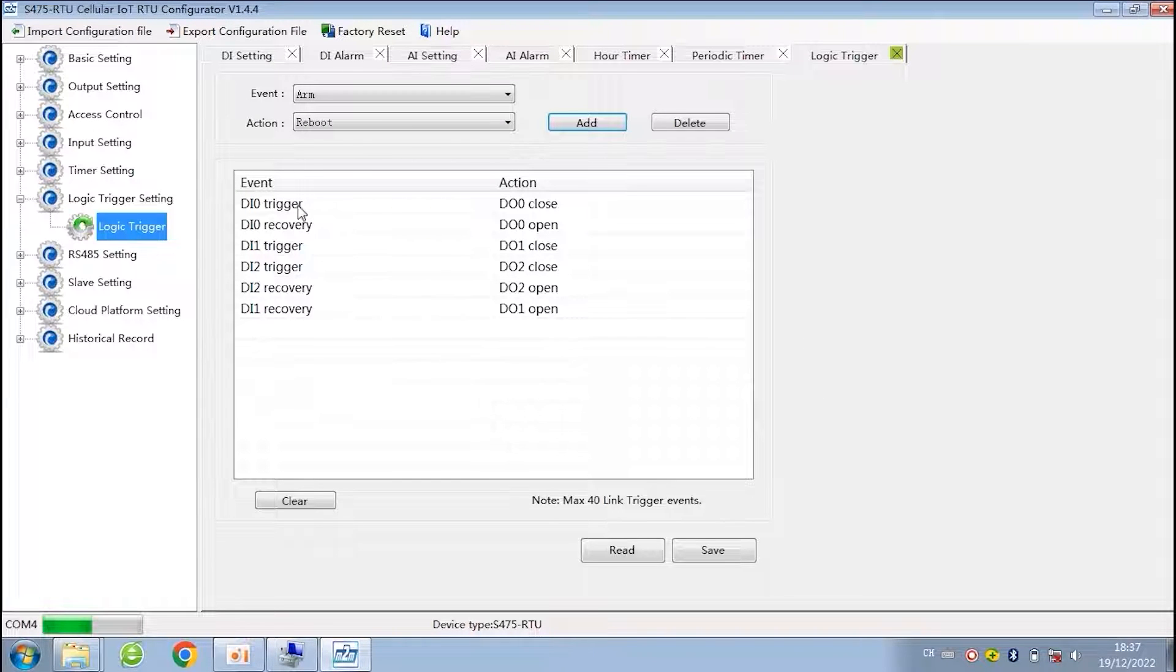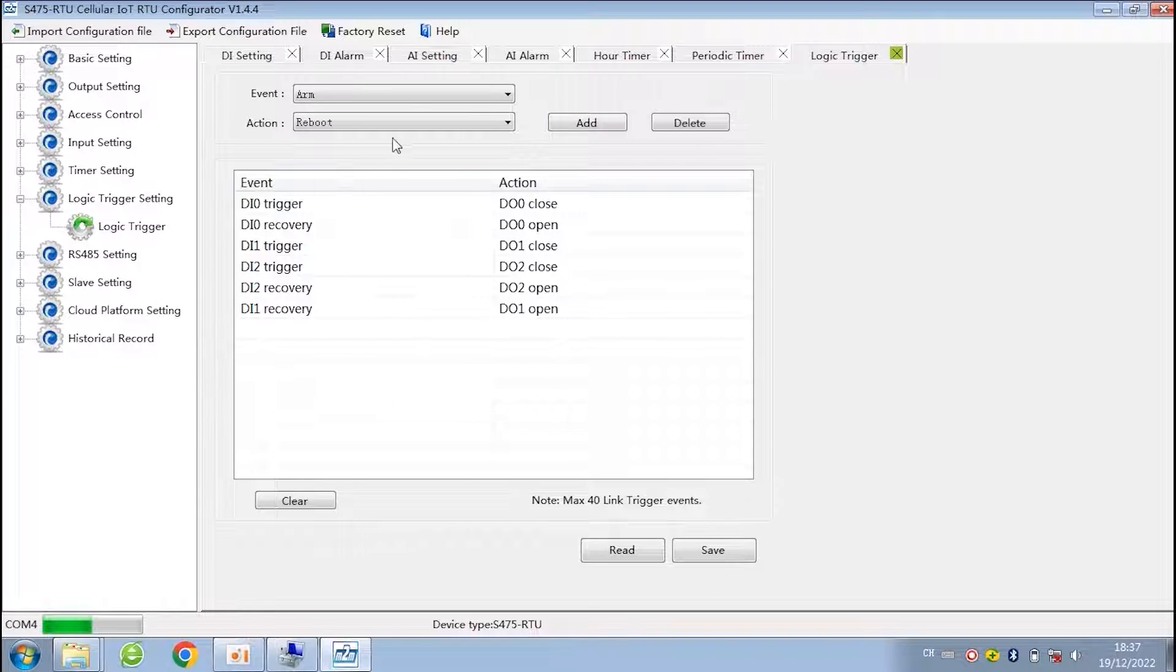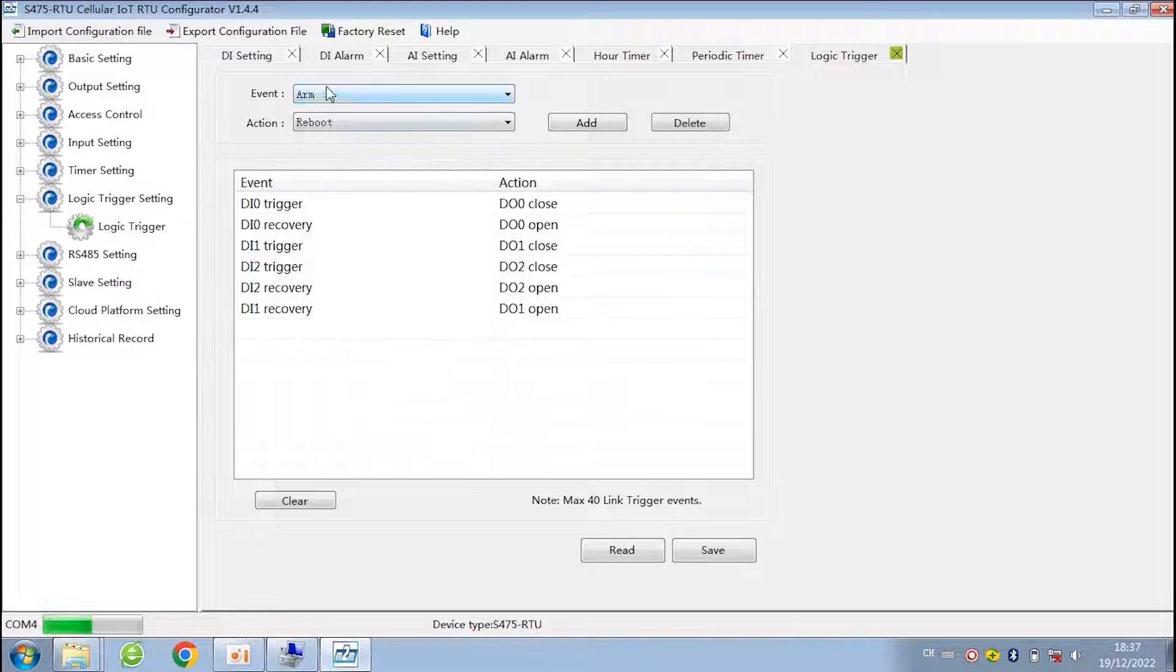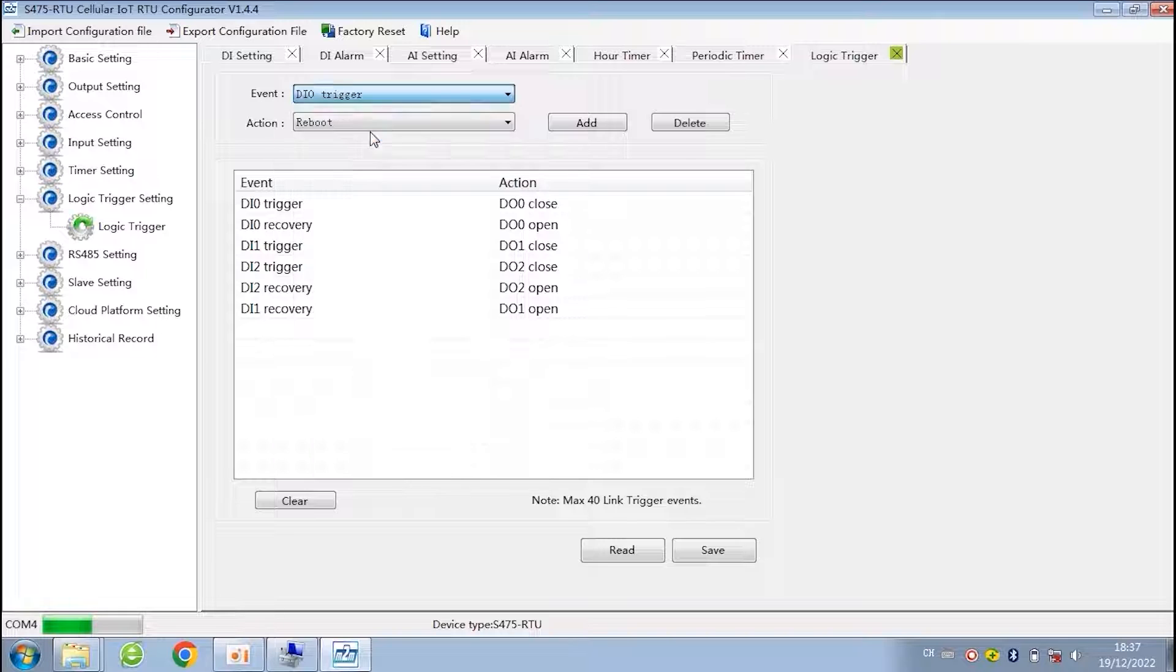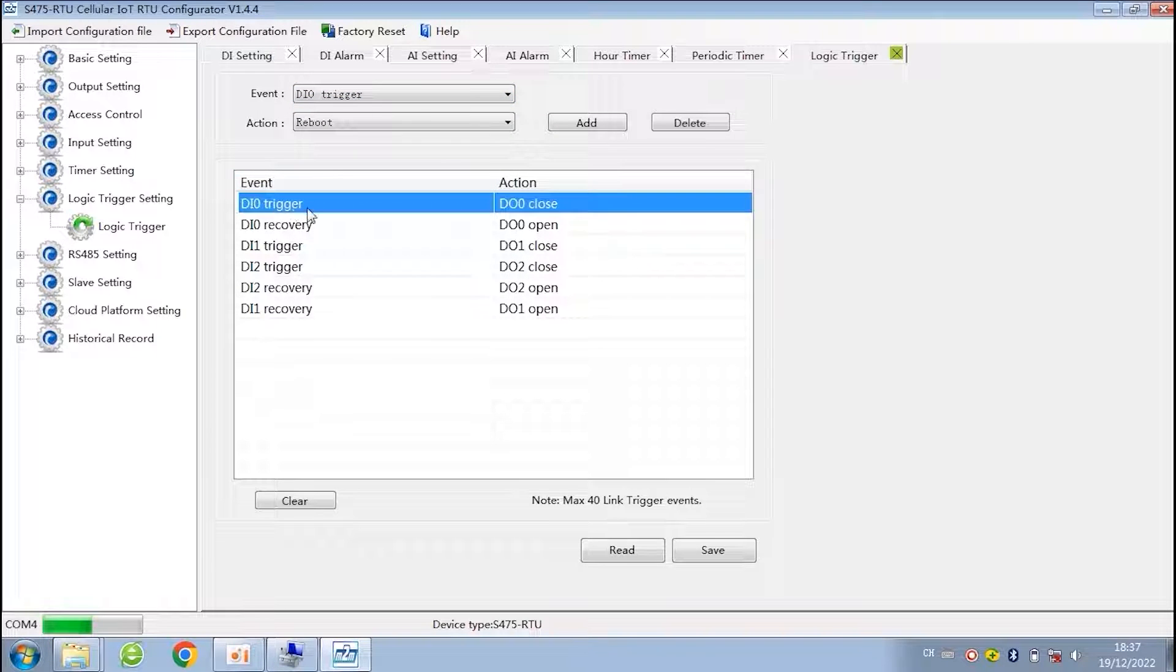Next is logic trigger. It means one event trigger one action. For example, when DI0 alarm, the DO0 will close. When DI0 recover, then DO0 will open. This is only for the data point of this RTU.